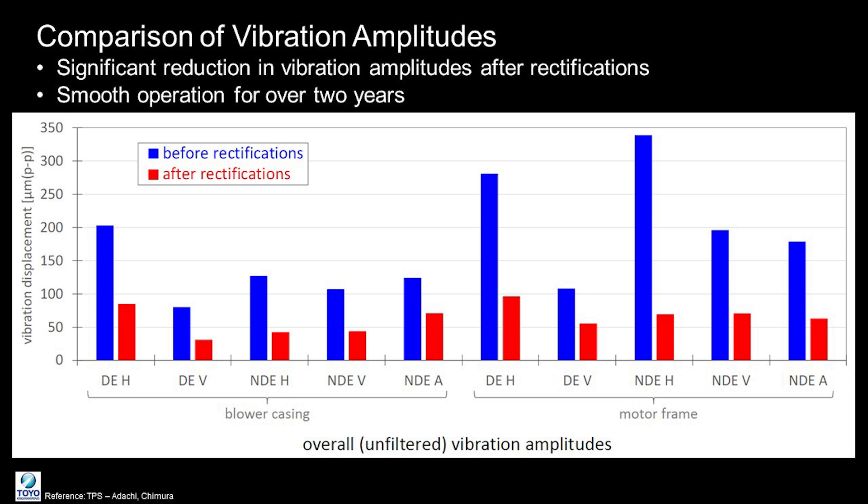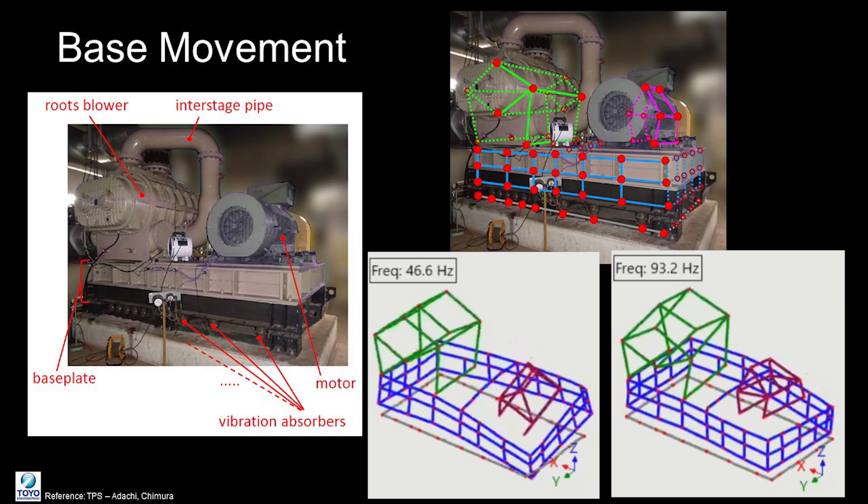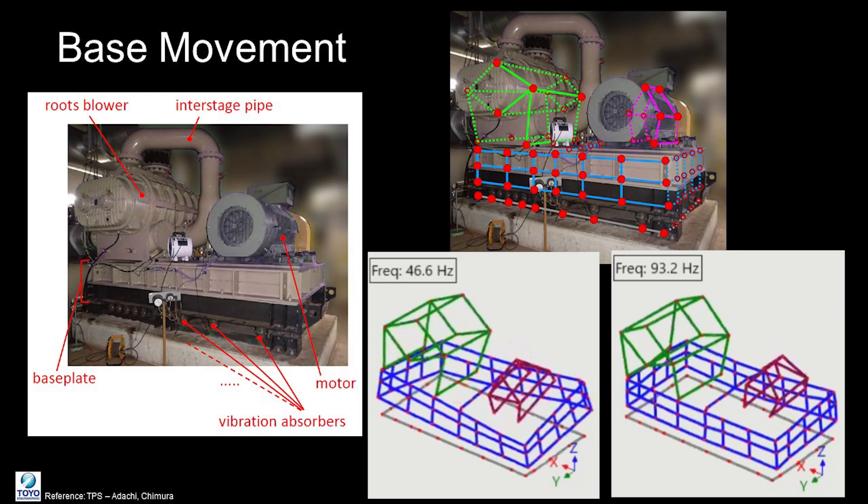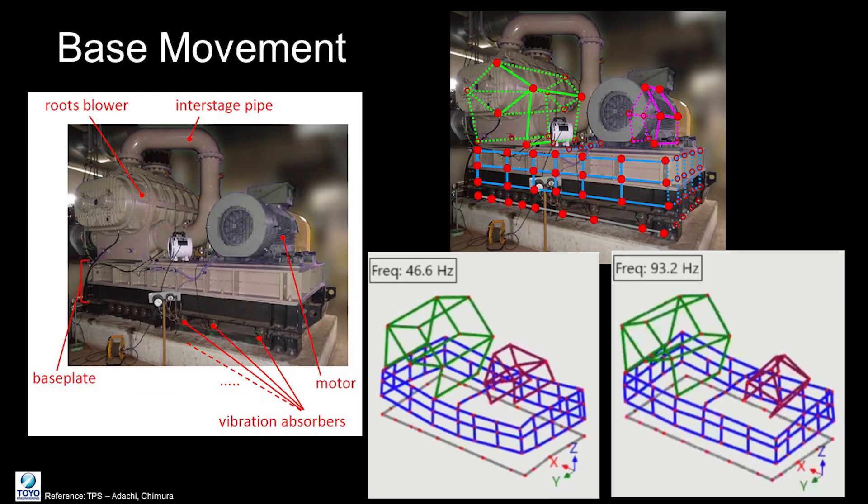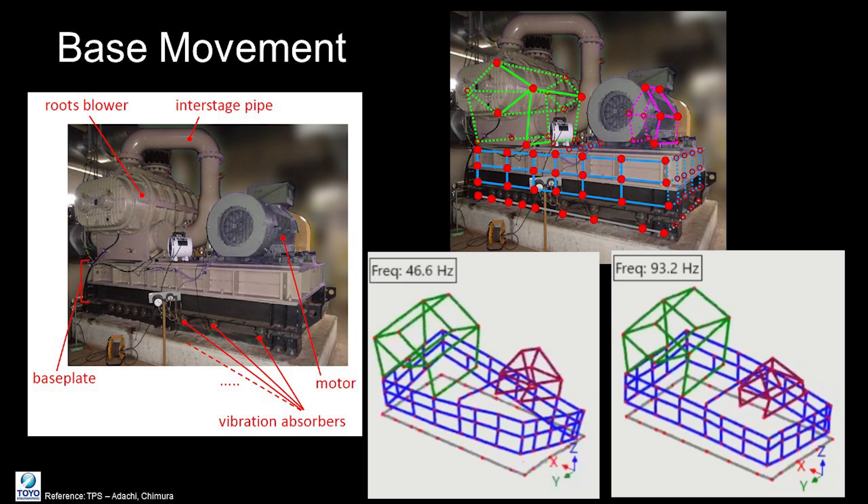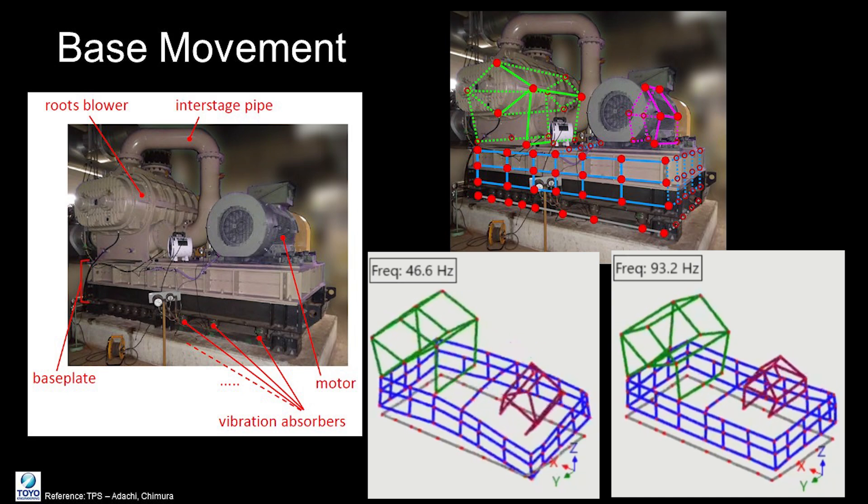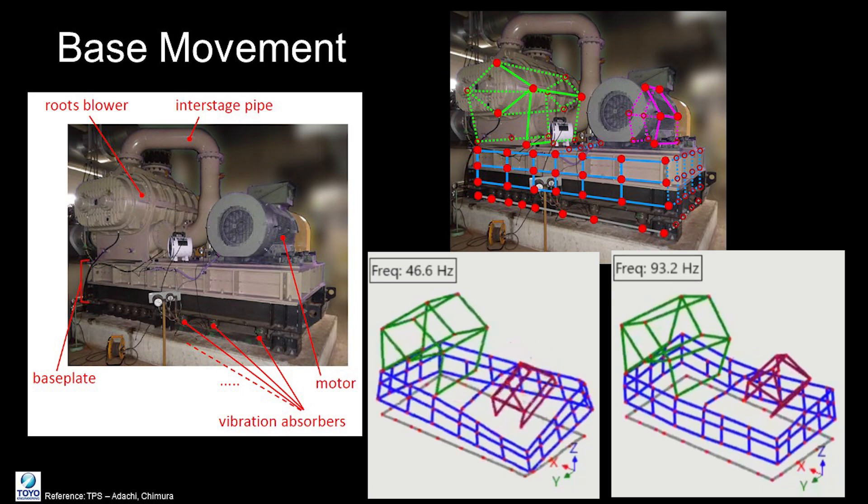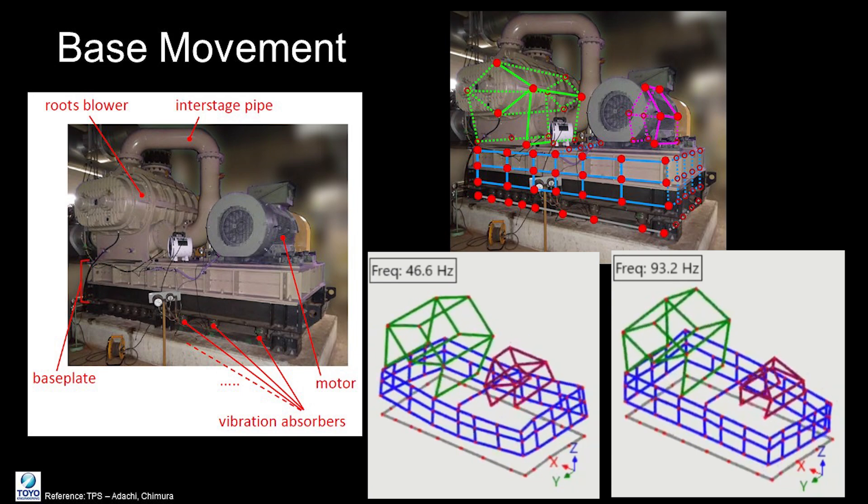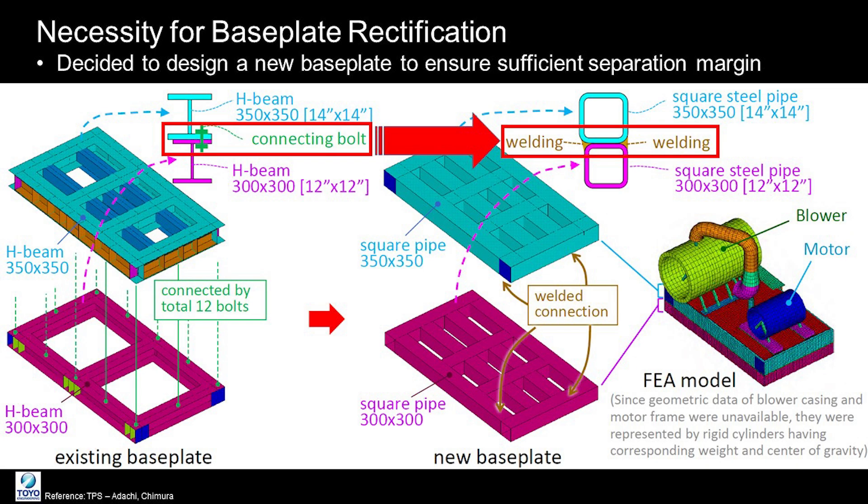Today's case study showed vibration issues stemming from structural resonance and excessive excitation. The modal analysis and video-based motion enhancement technology identified the exact sources of vibration. Implementing a new base plate and realigning the pipes successfully eliminated the problem.